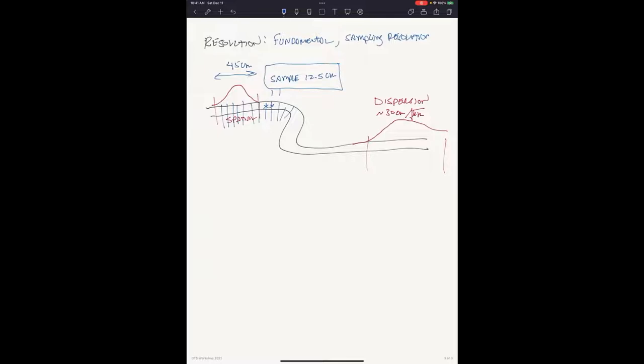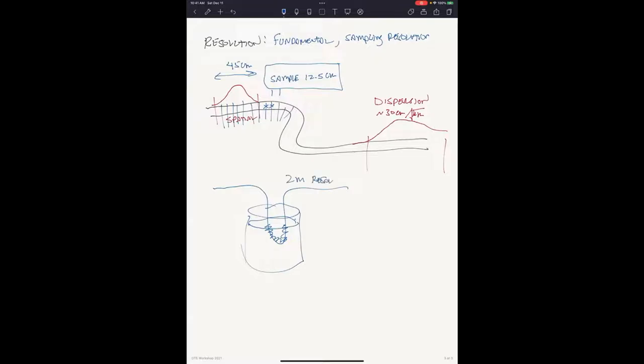In an interesting study, someone dunked a chunk of cable into an ice bath, but only a small section of cable was in the water, and they used a two-meter resolution device. When your true resolution is larger than the feature you're trying to measure, the instrument under-reports temperature because it averages in all the surrounding temperatures. The published report concluded the instrument didn't work, but that was because they fundamentally weren't respecting the fact that the spatial resolution of the system was much larger than what they were trying to resolve.